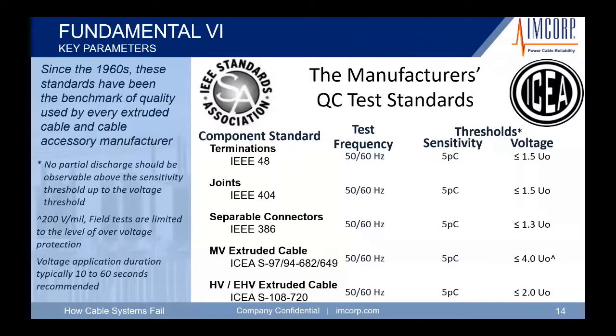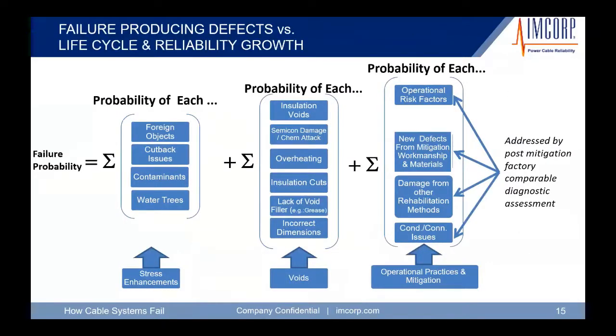It's when we take a component as well as a conductor, and we put those two together. That's when we see contamination in the cable accessories of the cable, as well as cutbacks. We see the workmanship issues that seem to plague us in most industries today. So we know that cables are inherent, because they're exposed to a lot of situations out there, whether it be foreign objects or voids, and these are brought in by the guys that are installing these, and then the operational practices of the application that it's in.